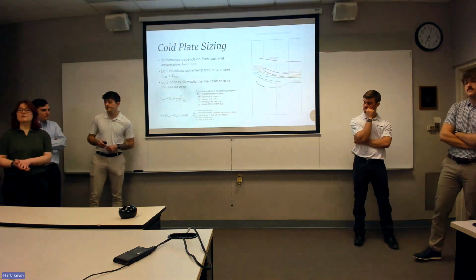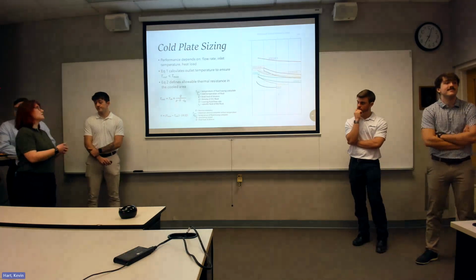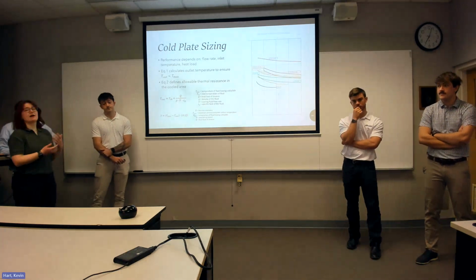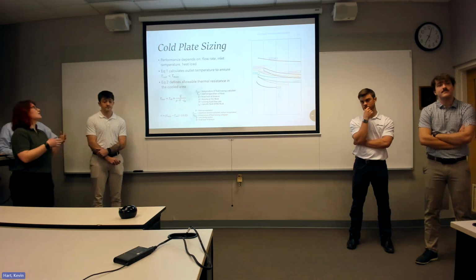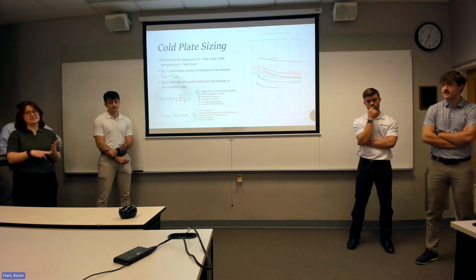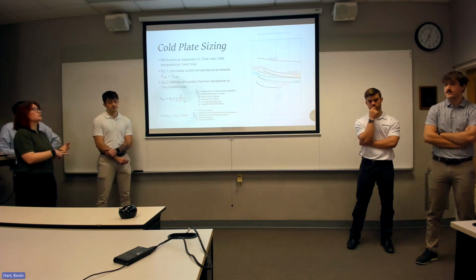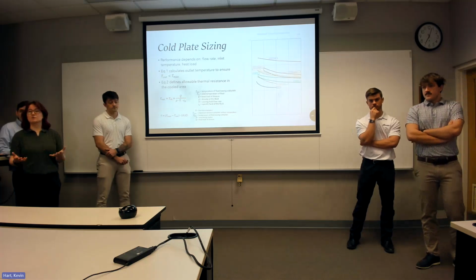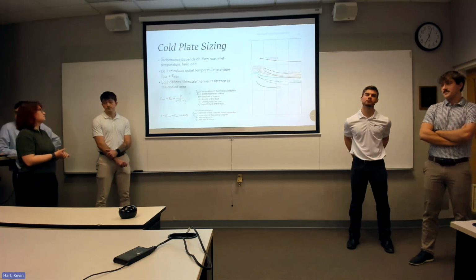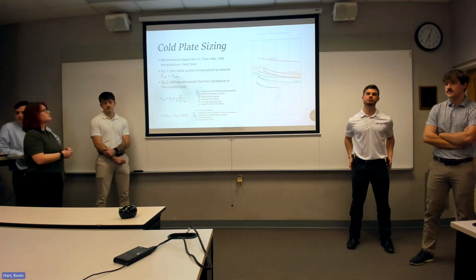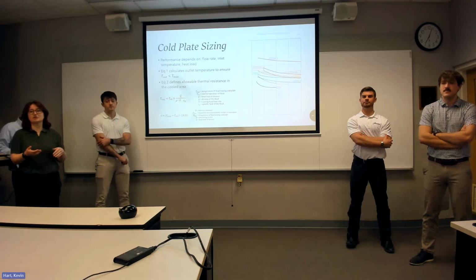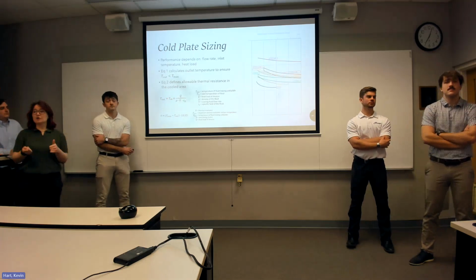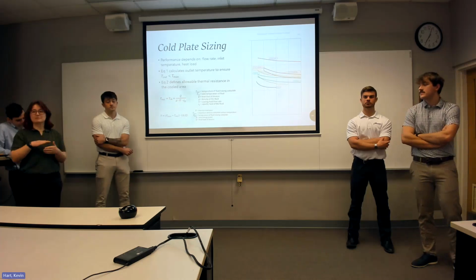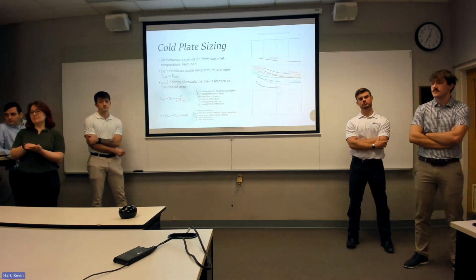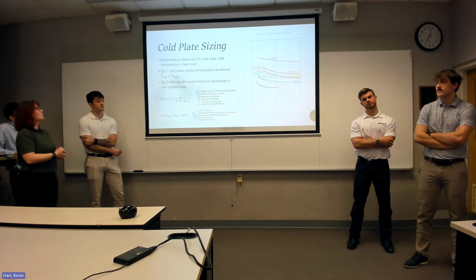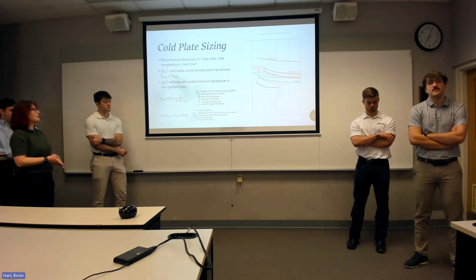Once we decided we wanted a cold plate, we looked into the performance and how those are sized by manufacturers. Cold plates depend on the flow rate, the inlet temperature, and the heat load. The first two we can experimentally control, and the third is what we're trying to find or control. Equation one calculates the outlet temperature to make sure the water coming out of the cold plate is cooler than the maximum temperature we're trying to achieve on top of the board. The second equation defines the allowable thermal resistance of that cooled area.